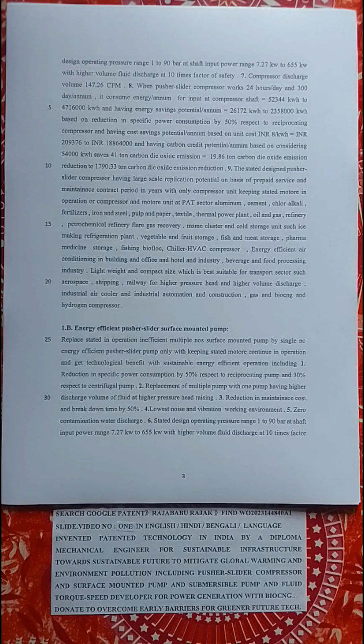1B. Energy efficient pusher slider surface mounted pump. Replace the inefficient multiple surface mounted pumps in operation with a single energy efficient pusher slider pump, keeping the stated motor in continued operation, and get the technological benefit of sustainable energy efficient operation, including reduction in specific power consumption by 50% with respect to the reciprocating pump and 30% with respect to the centrifugal pump.